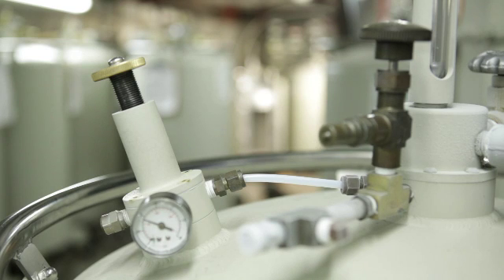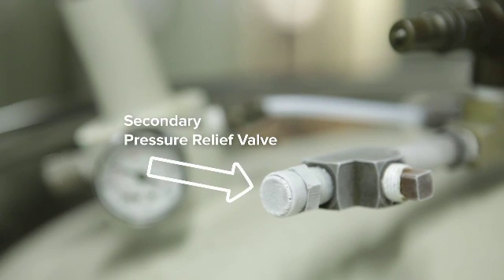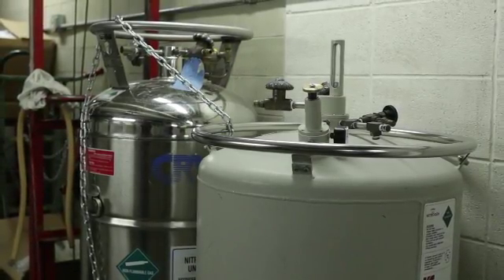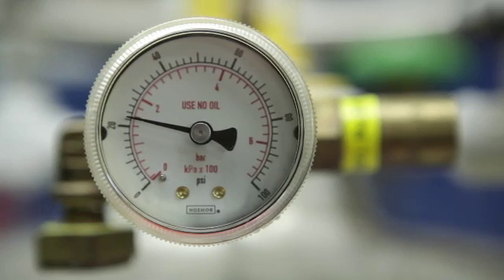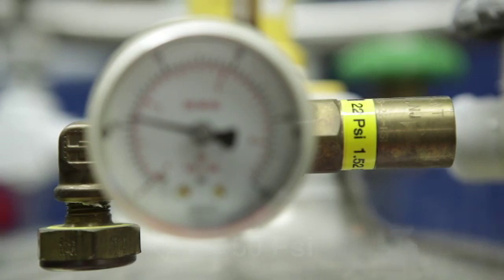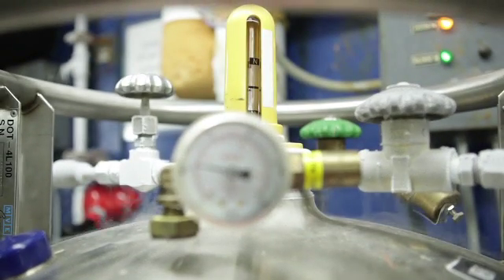The secondary pressure relief valve is set at a higher pressure. On this tank, this valve is installed on an extended stainless tube to ensure its opening if the primary relief valve is blocked by ice buildup or fails. If both relief valves fail or are not able to handle the pressure, a burst disc at the bottom of the tank may blow out and vent the pressure to prevent a tank rupture. The primary and secondary pressure relief valves on this tank are set at approximately 20 psi and 50 psi. Other liquid nitrogen tanks may be rated for higher pressure settings, so be aware of the specifications for your tank.